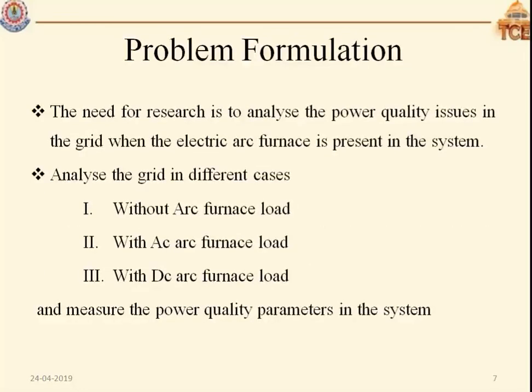In the problem formulation, we have developed two models. The first one is the AC arc furnace model using the hyperbolic EAF method, and the DC arc furnace model using the Cassie-Mayr arc furnace equation theory. We analyzed the grid in different cases: without electric arc furnace load, that is without any non-linear load, with AC arc furnace load, and with DC arc furnace load. We have studied three cases, and the power quality parameters are measured and validated.